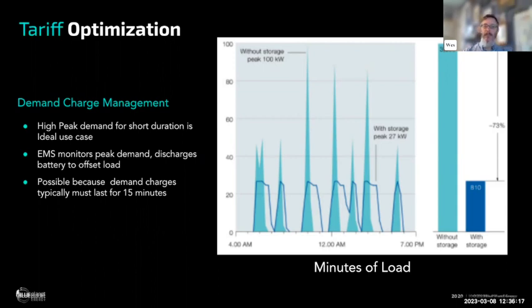With storage, the battery will discharge when the load starts. We do this with software, and it will absorb that high peak by discharging batteries at the same rate at which the load is coming on. So what the utility sees is just this low, something around 25 kilowatts instead of 100.